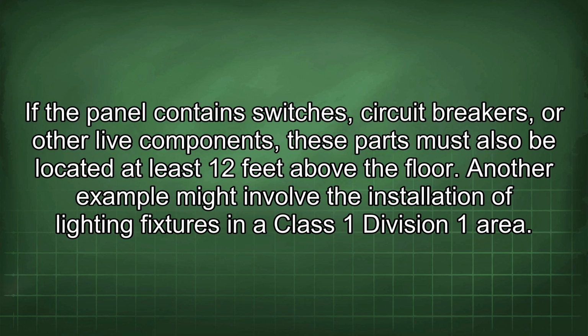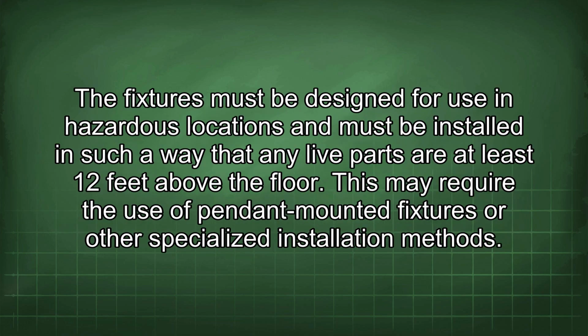If the panel contains switches, circuit breakers, or other live components, these parts must also be located at least 12 feet above the floor. Another example might involve the installation of lighting fixtures in a Class 1 Division 1 area. The fixtures must be designed for use in hazardous locations and must be installed in such a way that any live parts are at least 12 feet above the floor.